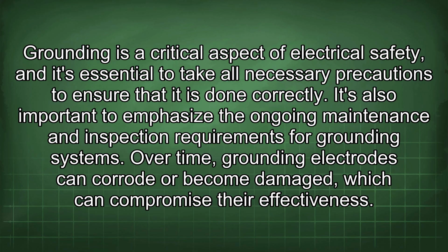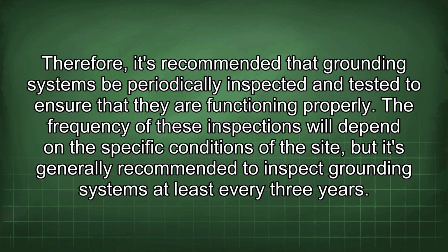is done correctly. It's also important to emphasize the ongoing maintenance and inspection requirements for grounding systems. Over time, grounding electrodes can corrode or become damaged, which can compromise their effectiveness. Therefore, it's recommended that grounding systems be periodically inspected and tested to ensure that they are functioning properly. The frequency of these inspections will depend on the specific conditions of the site, but it's generally recommended to inspect grounding systems at least every 3 years.